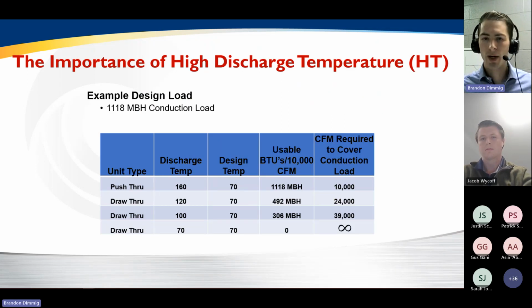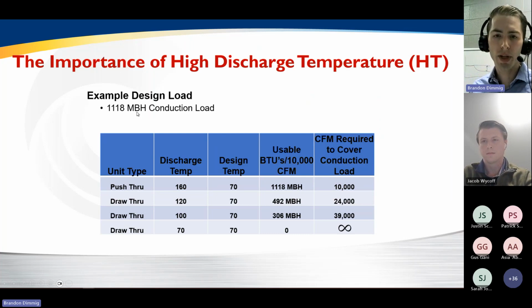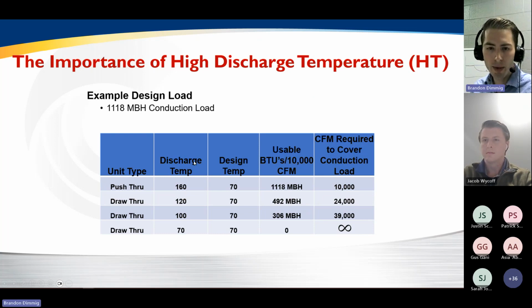So just looking at that comparison a little bit more, we'll take a theoretical building that has an 1100 MBH conduction load. If we were to use a 160-degree discharge temp unit on an internal design temp of 70, that unit needs to move 10,000 CFM of air. If you lower the discharge temperature, you're lowering the usable BTUs. And the only way to get that back up to meet the conduction load is to increase the CFM, or the airflow, of the unit. And so you can see that in order to hit the same usable BTUs, that unit would have to move 24,000 CFM of air because of that lower discharge temperature.